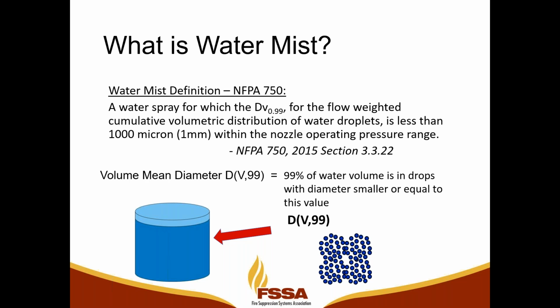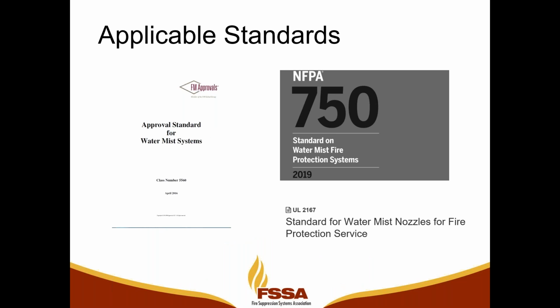Next slide. So there are several different applicable standards that govern water mist type systems. FM Approvals, which is heavily involved in approving these types of systems, providing their listings and doing fire tests, lists these particular types of systems under FM 5560. As mentioned before, NFPA 750 is the standard on water mist fire protection systems, and UL does have a slight entry into the water mist realm, where they list a water mist nozzle or spray head or sprinkler head under UL 2167 for ordinary hazard 1 type occupancies.